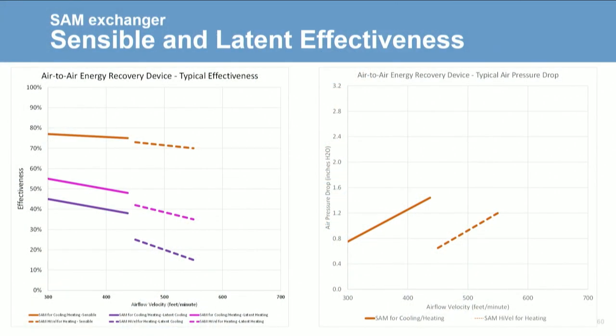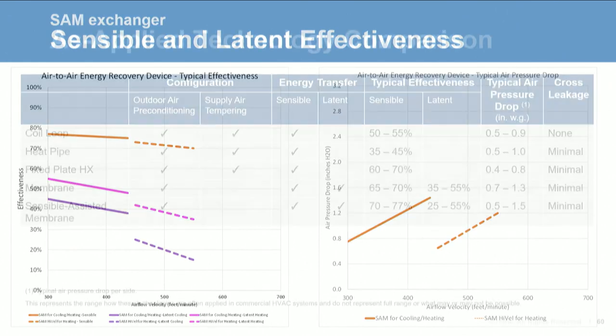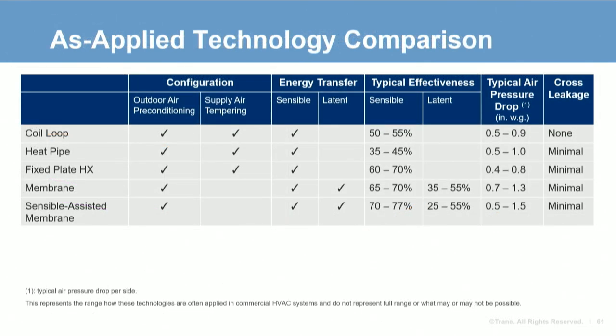As with metal plate exchangers, sensible effectiveness does not change much with face velocity, but face velocity does have a large impact on pressure drop. Summarizing in the table, SAM exchangers will have the highest as-applied sensible effectiveness, with latent effectiveness similar to membranes, or they can have similar sensible effectiveness to a metal fixed plate exchanger but still have some latent effectiveness.